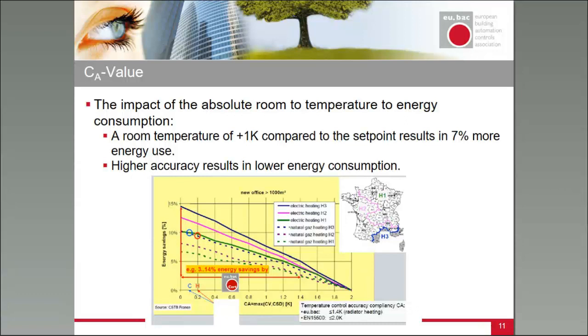Let's go to a control accuracy representative for the controllers we are testing, about 0.2. With 0.2, you get an increase in energy efficiency of around 10%, compared to a control accuracy of only 2 Kelvin. On the other hand, a change of room temperature by 1 Kelvin leads to a change in energy use of about 7%.